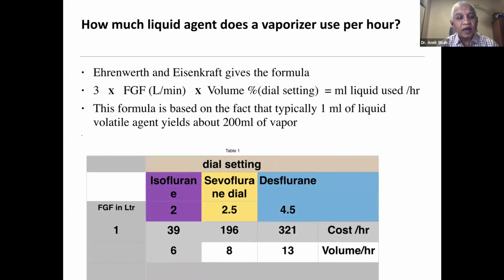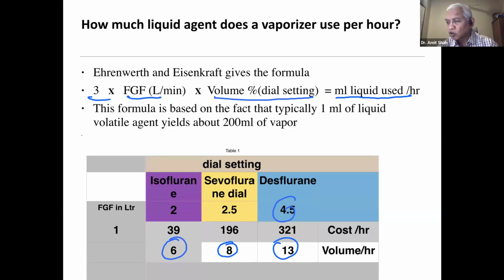Okay. So if you set a 1 liter fresh gas flow and a 2% dial concentration, what you will use for isoflurane is 6 ml. For sevoflurane, if you dial it slightly higher, it would be 8 ml, and desflurane would be 13 ml of volume. And then of course you can calculate the cost from that based on the purchase price which you have in your institute. So you can easily identify the ml of liquid which is used from the vaporizer based on the dial concentration which you have set and the fresh gas flow which you have used. Okay.